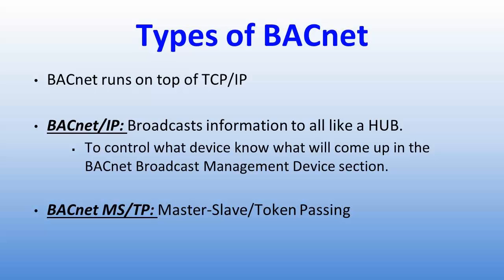There are different types of BACnet, which are BACnet/IP and BACnet MSTP. BACnet/IP runs on top of the TCP/IP protocols. BACnet/IP broadcasts information just like a hub, which broadcasts all that information to every single device that is on that network. Control of what devices know what will come up in the BBMD section.